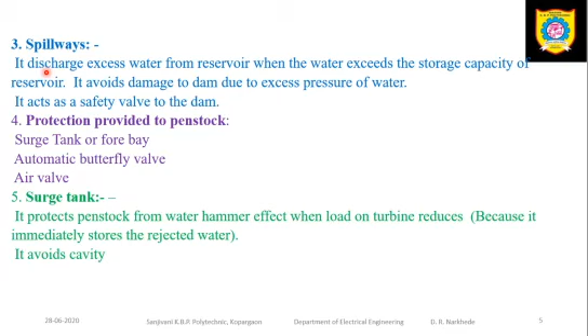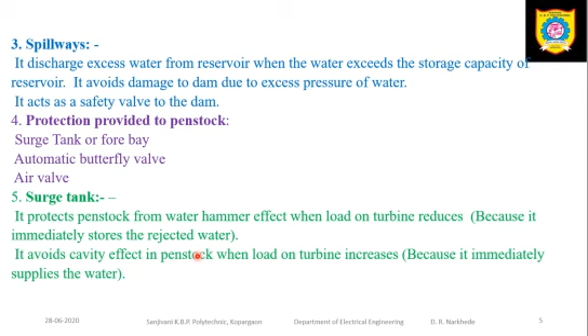Then protection for the penstock. We use the surge tank or forebay for the protection of the penstock. Then an automatic butterfly valve is also used, and air valves. So what is the surge tank? The surge tank protects the penstock from the water hammer effect when the load on the turbine reduces or increases, because it immediately stores the rejected water. It avoids the cavitation effect in the penstock when the load on the turbine increases, because it immediately supplies the water. So these are some of the safety practices used at a hydroelectric power plant.